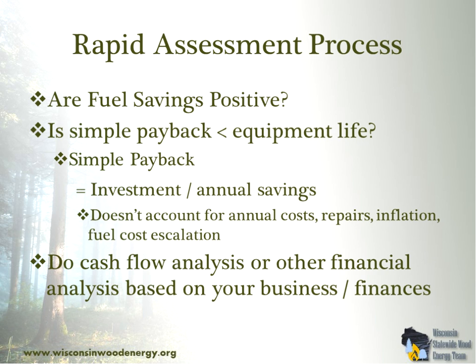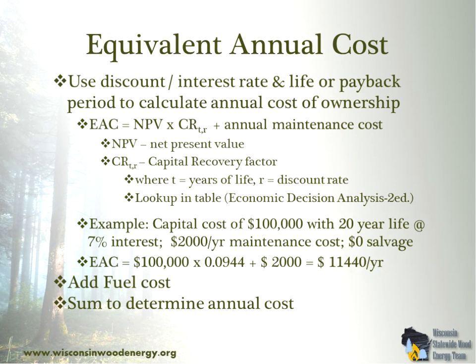So the first question, looking at this, is my fuel savings positive? If it's negative, then it's a non-starter. You're not going to do it. Then the second question is, what's my simple payback? Is it less than the equipment life? So simple payback is investment cost over the annual savings. So if I look at all those costs that I just had in the previous slide and divide that by my savings, if it's 10 years, is the equipment going to last 10 years?